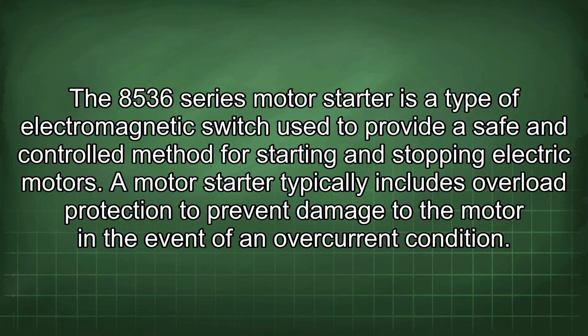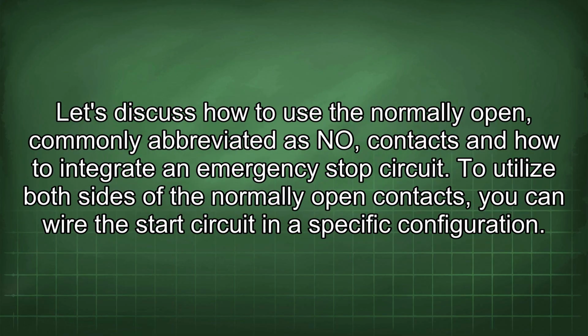The 8536 series motor starter is a type of electromagnetic switch used to provide a safe and controlled method for starting and stopping electric motors. A motor starter typically includes overload protection to prevent damage to the motor in the event of an overcurrent condition. Let's discuss how to use the normally open, commonly abbreviated as NO, contacts and how to integrate an emergency stop circuit.